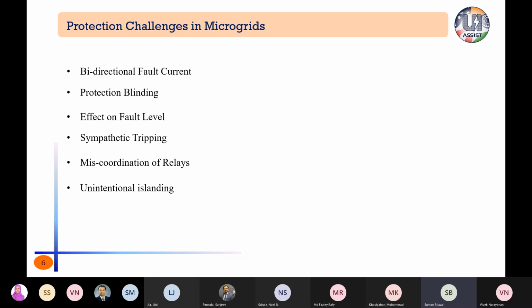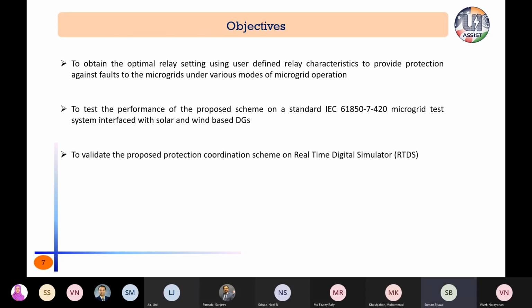So unintentional islanding of DGs is also one of the major challenges in microgrids. Our objective is to provide optimal settings of the relay, and here we are proposing non-standard tripping characteristics. That is, not standard. We'll see the standard characteristics as well, but here we are proposing user-defined or non-standard tripping characteristics to provide protection for various modes of microgrid operation.